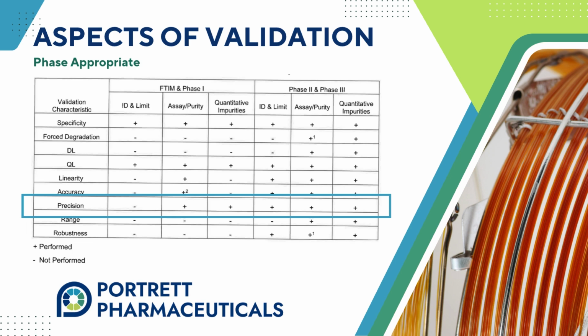It is important to consider the method and how the variations that are included in the evaluation may affect the results. We had an issue where a different sonicator was used by the second analyst. That sonicator produced more heat and caused the impurity results to be significantly different than the other analyst. So think about all the steps and what's important to be evaluated when developing your protocol.